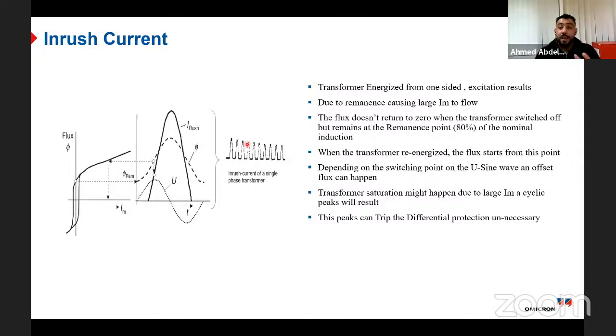Here you can see the magic of the numerical relay. In the old high impedance scheme, there was no way to detect the inrush. At that time, we just increased the setting of the relay to a very high value, then energized, then reduced the setting again after energizing to avoid tripping on the inrush. But with the numerical relay, we can have this value. We can estimate.